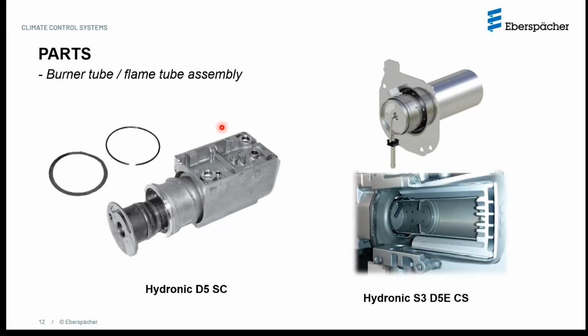Here we have the burner tube or the flame tube assembly. This is basically where the fuel air mixture is ignited, and this is where the combustion process happens. The difference between the two burner tubes is that the newer generation is made of stainless steel sheet metal, whereas this was more like an investment casting. Of course, because it was an investment casting type part, the pricing on this part was much higher. So to reduce the cost of the overall unit, they started using stainless steel sheet metal. But you will see that they haven't compromised on the quality.